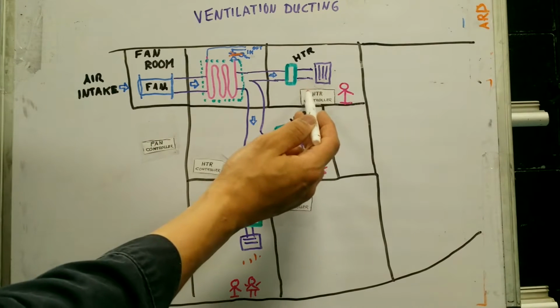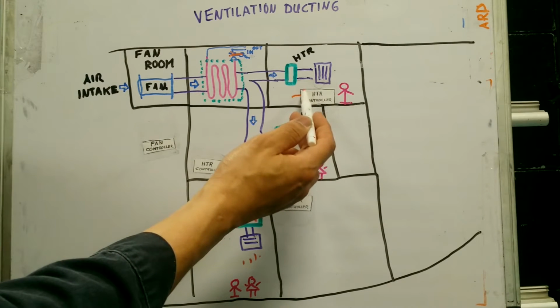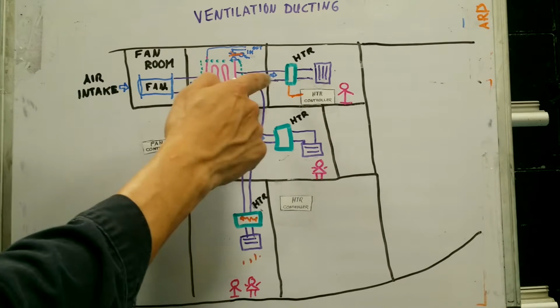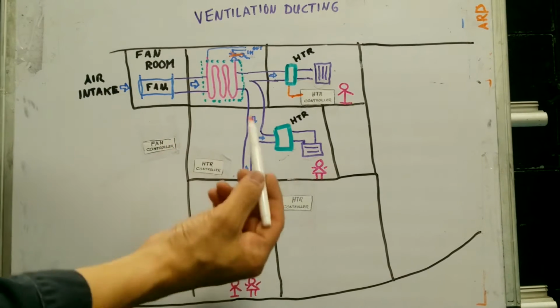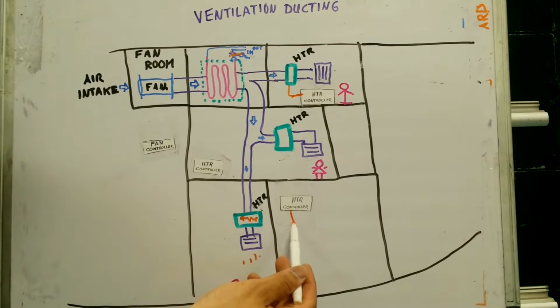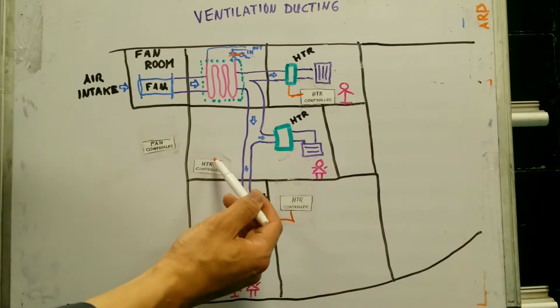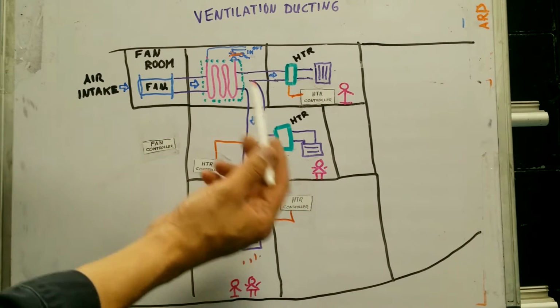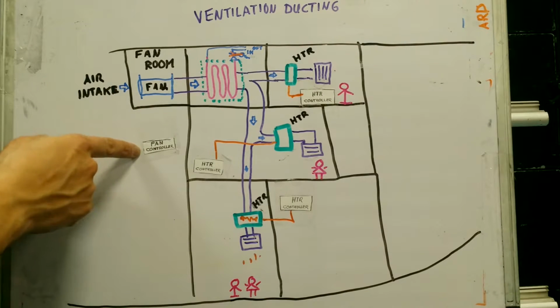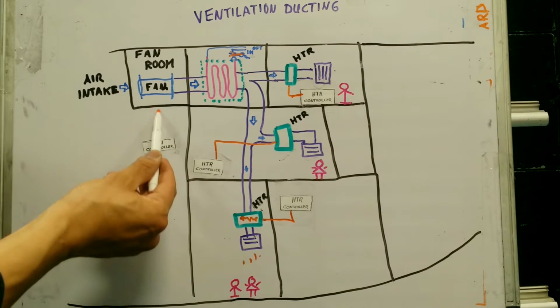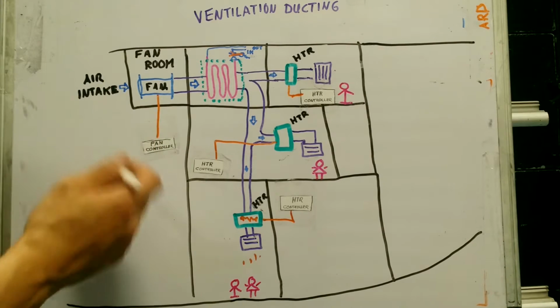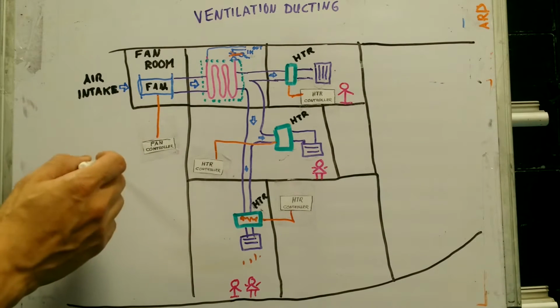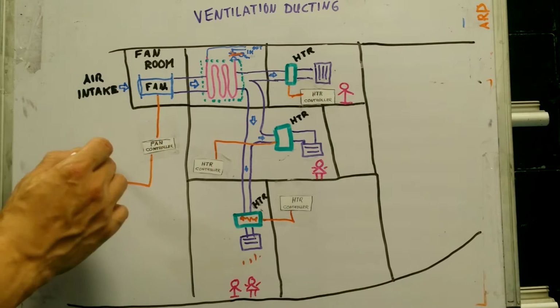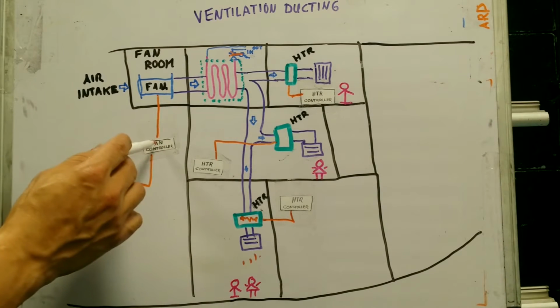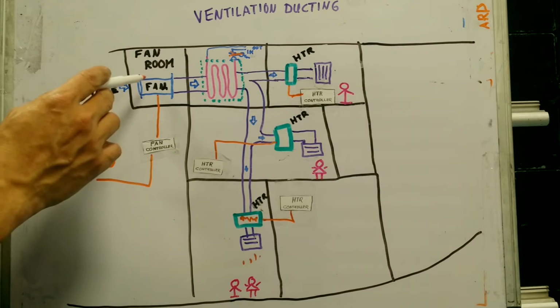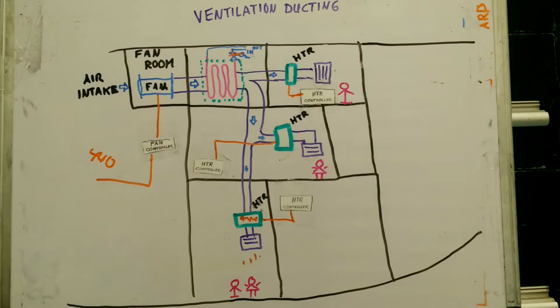They've got these heater controllers, and they energize the heaters. So they've got this heater controller that energizes this heater, and this heater controller energizes this particular heater. There is also a fan controller, and the fan gets controlled by its own controller. Now, there are multiple sources of power. There will be one 440 system that will give power to the fan controller, and that is also going to energize the fan itself.